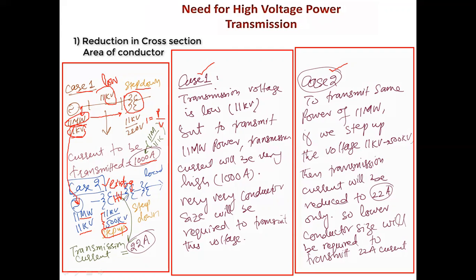By different stages, we will step down this 500 kV to 220 kV, then to 132 kV, 66, and so on to 11 kV. Now how much current will we need to transmit in this case? That would be 22 amperes, meaning 11 megawatts over 500 kV. So we will get 22 amperes, which is very low as compared to the first case.